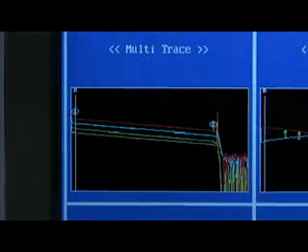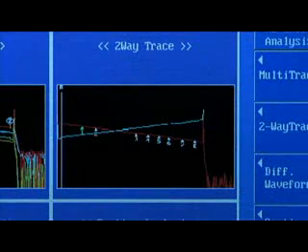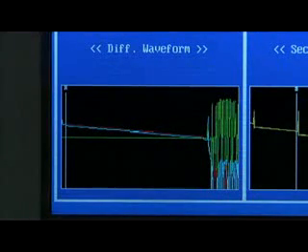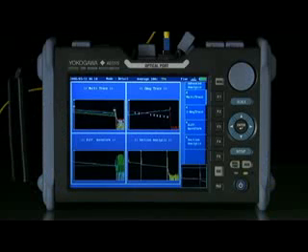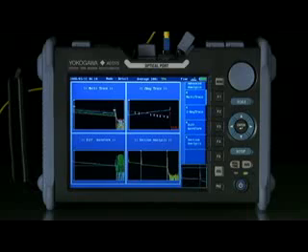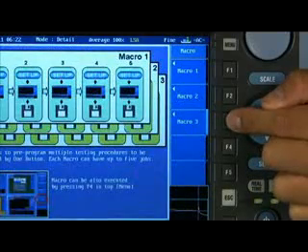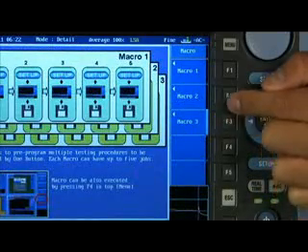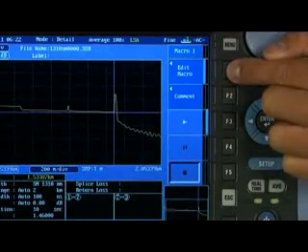Some of the more advanced testing scenarios include automated multiple-wavelength testing, two-way testing, making a differential measurement, and section analysis, while optionally autosaving on either internal memory or USB drive. For the novice user, our macros feature assures proper testing if more complicated tests are called for by your company's standards.